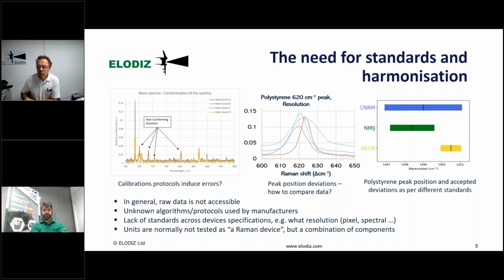For example, when you analyze the calibration protocols described in the different standards, you can see that there are plenty of problems, for example, with emission lines. The emission lines are not clean emission lines, unless you have a very expensive one. And even so, it's very difficult to differentiate which part of the spectrum corresponds to the real peak, and which is the error introduced by those contaminants. There is also the problem of reproducibility of the data. For example, this is one peak of polystyrene using 5 different instruments. Polystyrene is polystyrene, but there is a small difference between peaks.